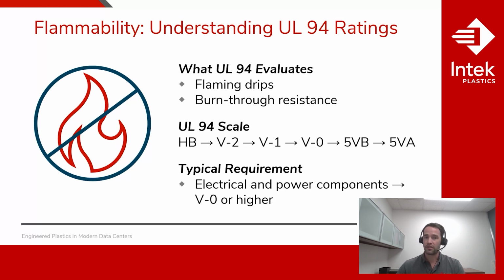Some polymers, such as PVC, are inherently flame retardant, so they tend to do quite well under these assessments. For other polymers, such as polycarbonate and ABS, these will typically require the addition of flame retardant additives to improve their performance. These fillers can also compromise mechanical properties and thermal performance. So it's important to understand how these fillers interact with your plastic so that you're not compromising other performance requirements. And understanding this early in the design process is really critical to ensuring the safety, compliance, and long-term reliability of these components in your data center.